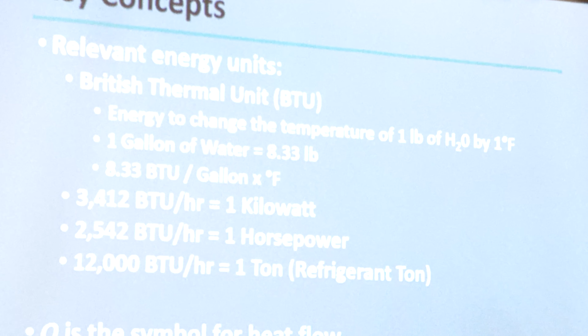So key overall concepts, the more technical part of it. You'll just hear me say BTUs, British thermal units, generally what we use to size for heating and chilling loads. 8.33 BTUs to heat 1 gallon of water 1 degree Fahrenheit. Some conversions to other common power units, the other big one, 12,000 BTUs for 1 refrigerant ton. Typically you see BTUs in heating, refrigerant tons in chilling. And then lastly, for anybody who didn't have to suffer through thermo, Q is energy flow, so you'll see that quite a bit throughout the presentation.